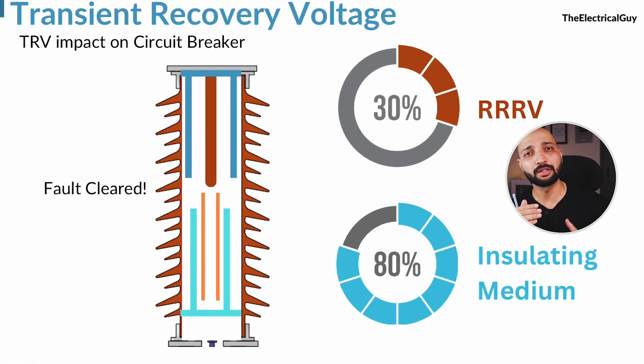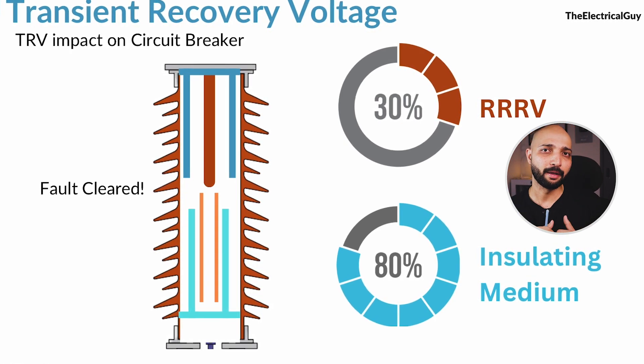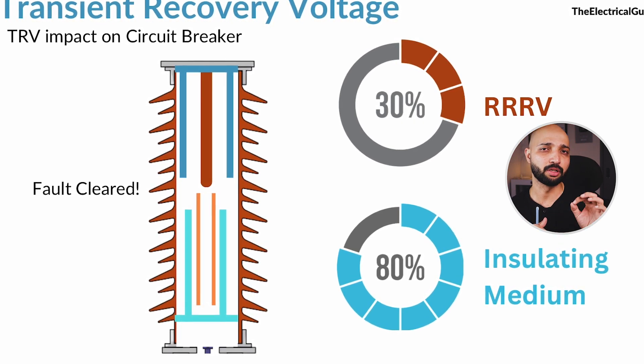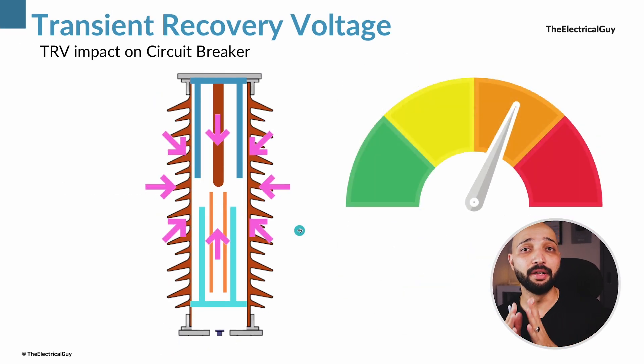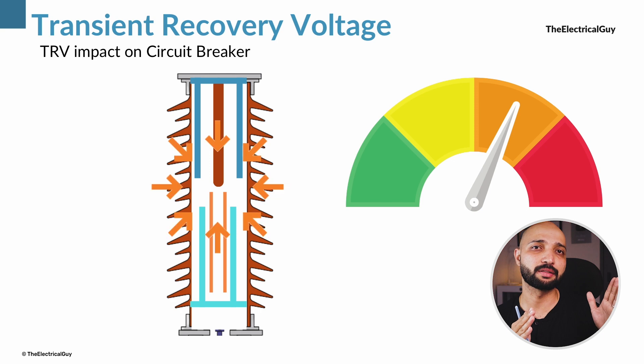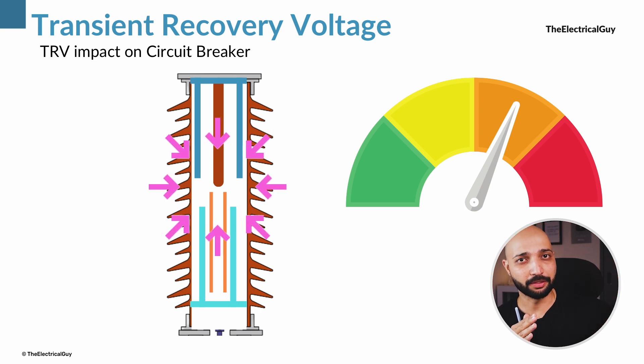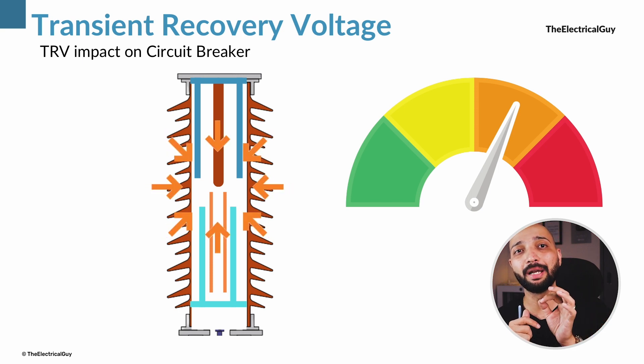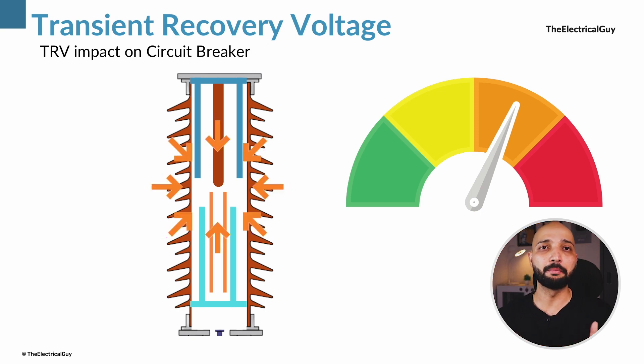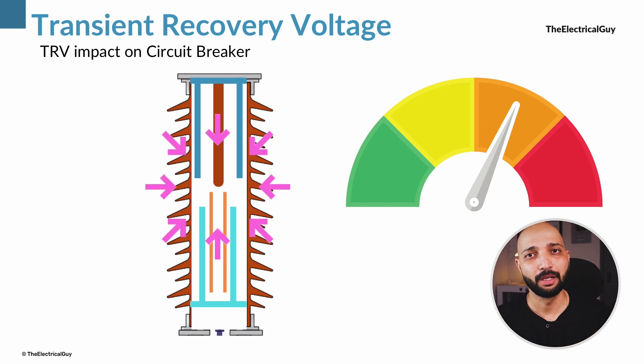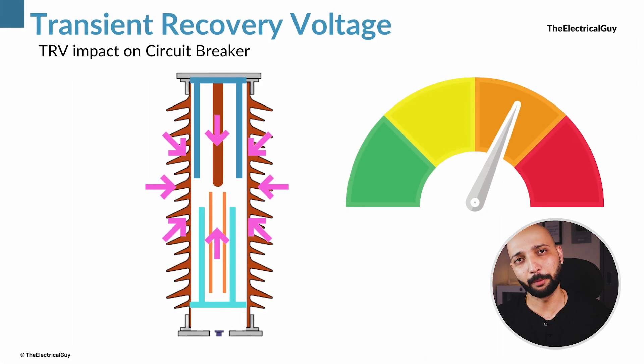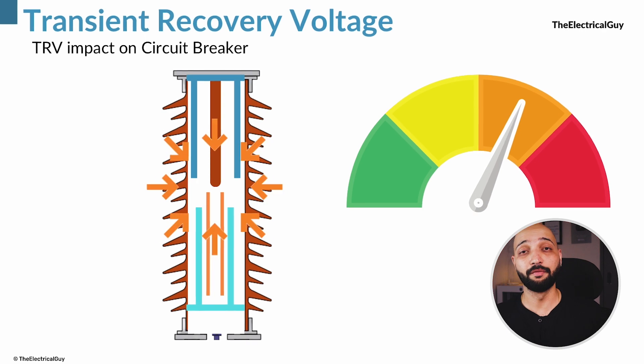This process of re-establishing current is called re-ignition, and it generally occurs almost immediately after current zero because the arc plasma containing conducting ions re-establishes current. If TRV is very high, it will stress the interrupting medium that has returned to its insulating state. If the electric field created across the contacts is very high, a dielectric breakdown may take place, causing the interrupting medium to become conducting and carry the current again — this process is called re-strike, and it generally occurs about a half cycle after current interruption.